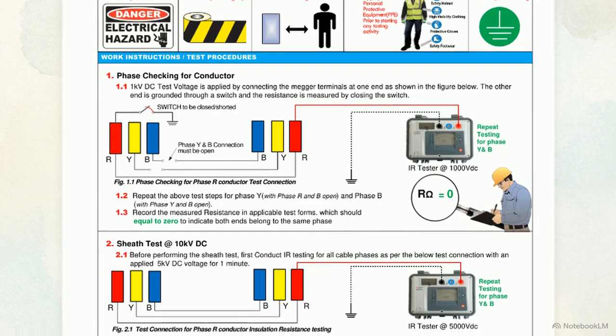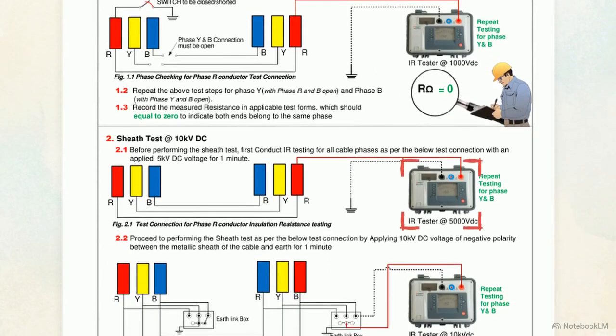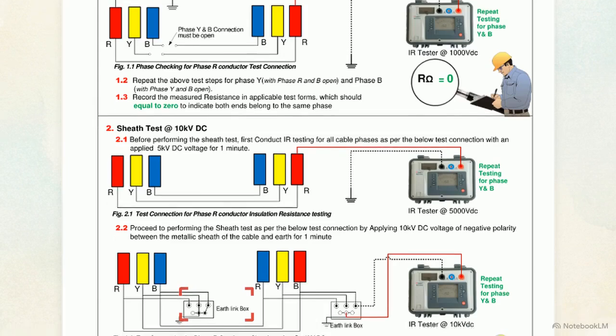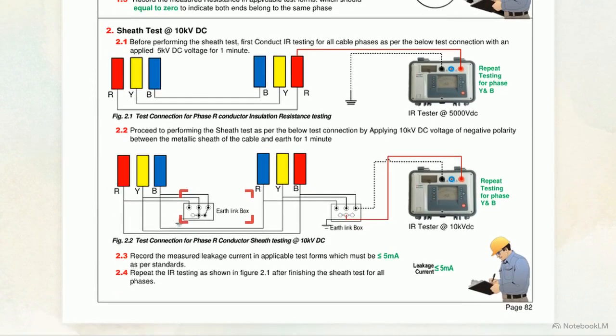Before the sheath withstand test, a 5 kV DC baseline is recorded for 1 minute. Apply 10 kV DC negative polarity between the metallic sheath and earth for 1 minute per phase. Acceptance requires leakage current below 5 milliamps.